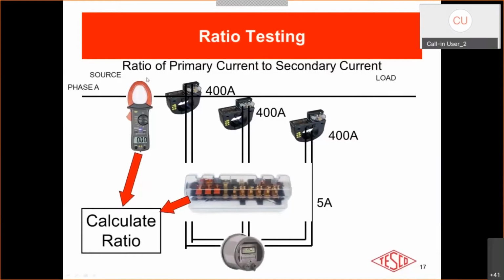You can use a simple Fluke or AMC style clamp handheld meter. But one caveat that you need to be aware of and be considerate of is if there's any time between the measurement of the primary current and the secondary current, if you have a fluctuating load, that might throw your numbers off. So various specialized custom ratio test units on the market take these two measurements simultaneously, thus negating a fluctuating customer load.